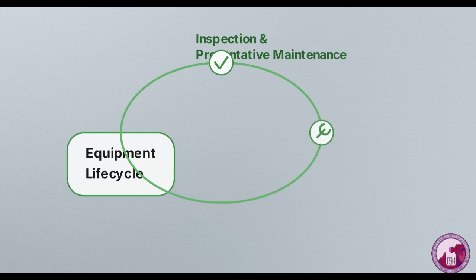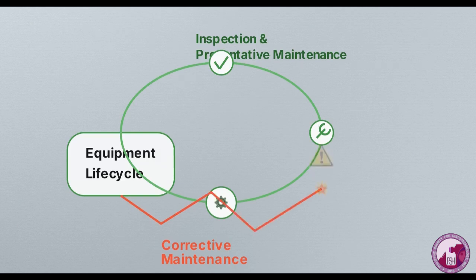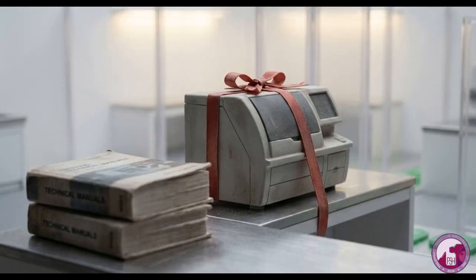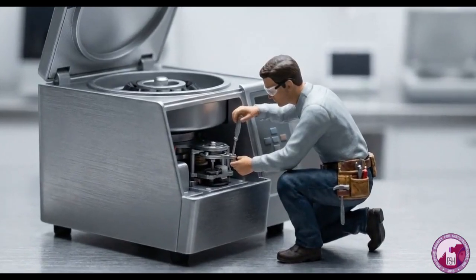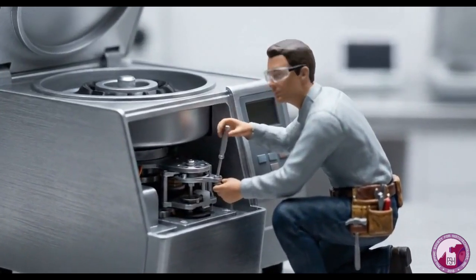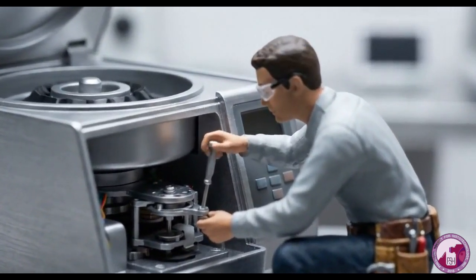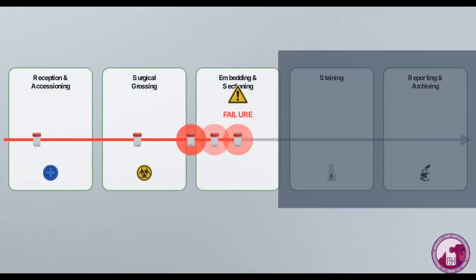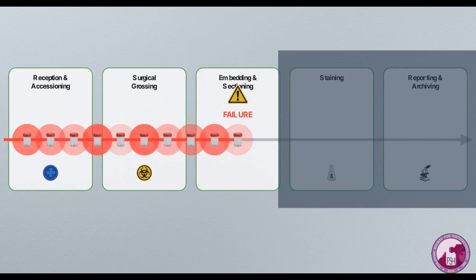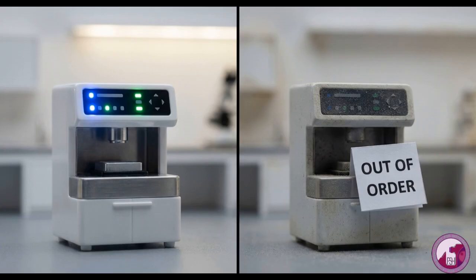These are proactive, scheduled activities, like calibration and cleaning, designed to extend device life. The second is corrective maintenance. This is the unscheduled, reactive effort to restore physical integrity only after a machine has completely failed. This dynamic explains why donated equipment in resource-limited settings often becomes a liability if it arrives without a funded service contract or specialized training. The local biomedical engineer serves a critical role here, performing preventative inspections and optimizing existing resources to keep the hardware running. A single failed machine, due to a lack of maintenance, creates a bottleneck that breaks the entire unidirectional workflow pipeline. Capital expenditure on infrastructure is wasted without a fully funded, structured maintenance and lifecycle management plan.